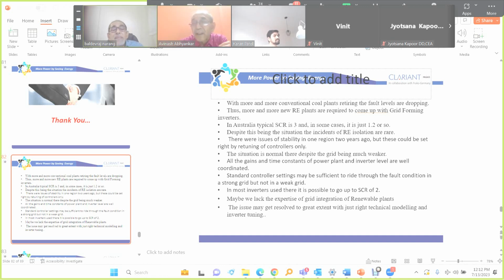Yes. You must have an energy source across the solar system, the PV panels, to support the reverse conducting currents from the AC grid. And unless you have that energy storage element, at least to the extent of what is required to feed the fault, and suppose the entire fault clearing process requires 2 minutes, 3 minutes, or 5 minutes, you need DC link capacitors across the solar panels for stabilizing your grid. Without that, you cannot handle the reactive power.